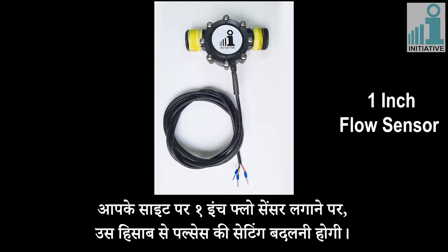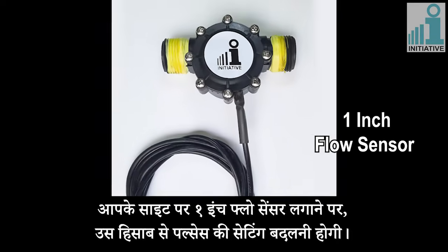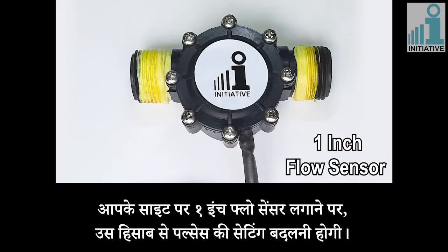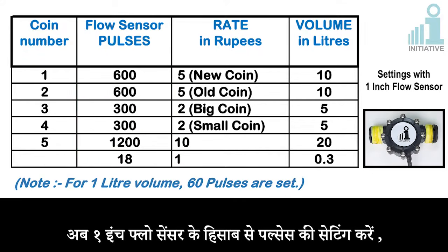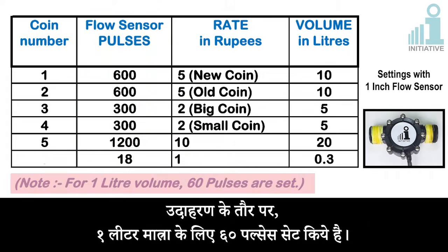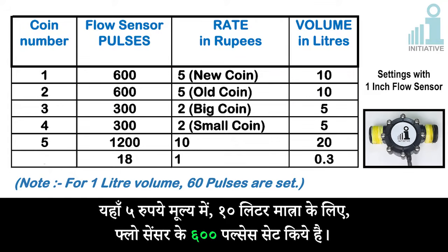After installing the 1 inch flow sensor, the pulses settings should be changed accordingly. Now set the pulses according to the 1 inch flow sensor. For example, for 1 liter volume, 60 pulses are set. So here, for the rate of 5 rupees and 10 liters volume, 600 flow sensor pulses needs to be set.